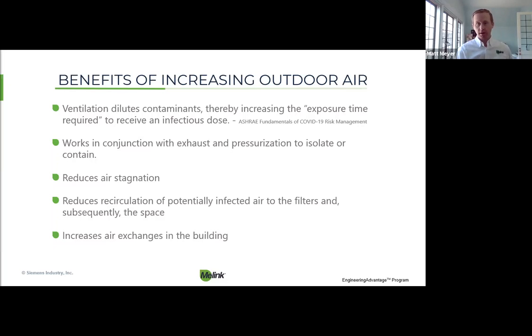Very important to consider with outdoor air: it needs to work in conjunction with your exhaust and the pressurization of your building. If you're going to increase the outdoor air, obviously you need to increase your exhaust at some point to keep that building at a decent pressurization. This reduces your air stagnation because you're not just recirculating the same air through your building all day long. And then the reduction of recirculation of potentially infected air is pretty self-explanatory as well. A lot of this stuff is pretty easy to grasp. And then it's an increase in the air exchange in the building. Of course, you'd rather have a building that is getting filtered air pulled through it at a more frequent pace than a less frequent pace.